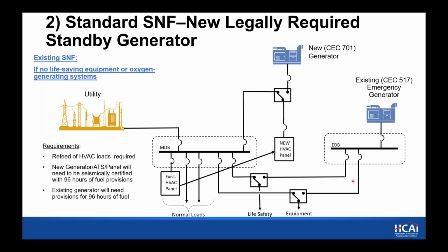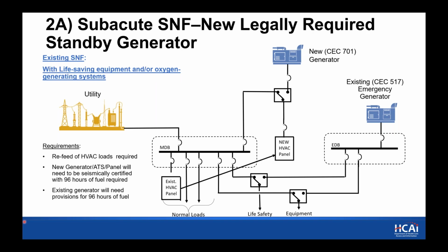Let me go to it. Now, this one, wouldn't this existing generator only require 6 hours of fuel because there's no life-saving equipment on it? Well, so our code for life safety is predicated that the life safety system will be fully operational for the duration of when the building is occupied and up to 90 minutes afterwards. So that's a really good question. And basically when we're saying we're putting the life saving and the cooling, then we're intending that this building is going to be occupied for 96 hours. And so we need the life safety systems to be operational for those 96 hours. A really good question. Thank you.